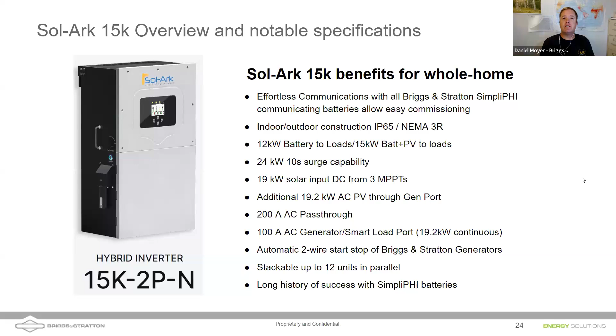We've been integrating with the Sol-Arks the whole time. The 200 amp AC pass-through is really the key takeaway of this training, that the ability to do whole home backup using energy storage systems is now possible with these hybrid inverters, just like a Sol-Ark that has this 200 amp pass-through. Until they had that, it was difficult to do a whole home backup. Also, the energy storage batteries, the 6.6 batteries, have come down in price and have that fast discharge rate to supply the home loads, which is what's made this possible. It really wasn't until recently that we've had both a high quality inverter and a high quality battery to do whole home backup. I see the future of a lot of our energy storage systems going forward being these whole home backup architectures. So excited to see any of your installs.